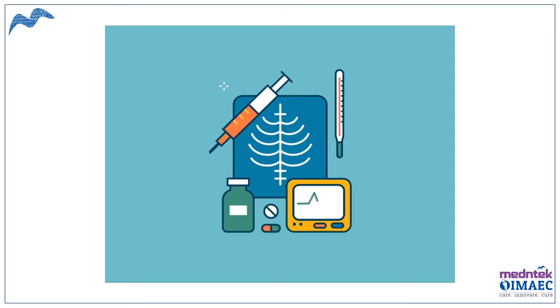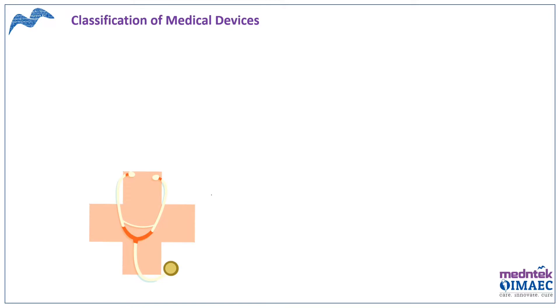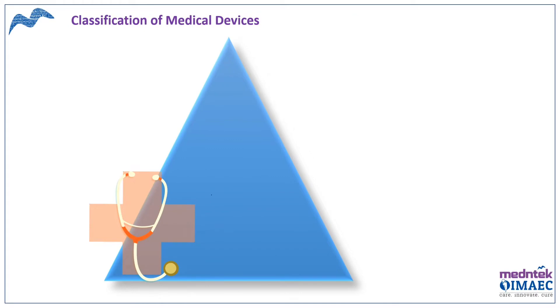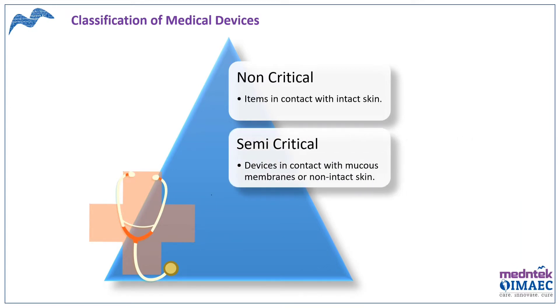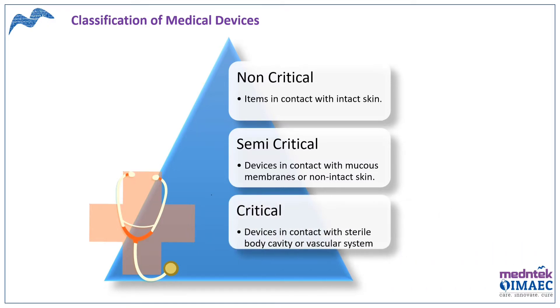Medical or surgical instruments also contribute to the spread of infection if not disinfected properly before every use. To define the disinfection strategies, medical devices are classified into three categories: non-critical medical devices which come in contact with the intact skin of the patient, semi-critical medical devices which come in contact with the mucous membrane or non-intact skin, and critical medical devices which come in contact with sterile body cavity or vascular system of the patient.